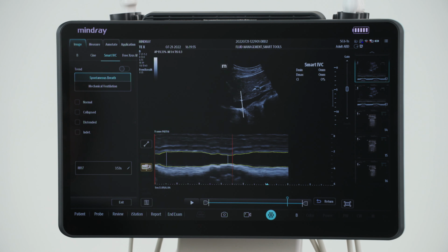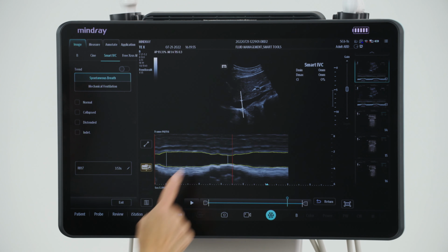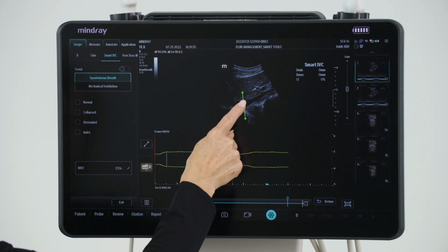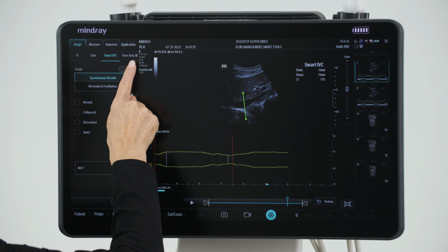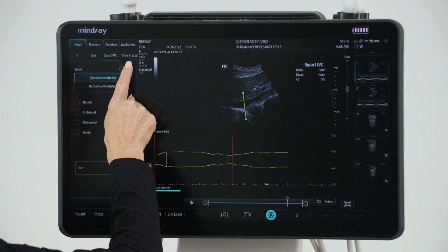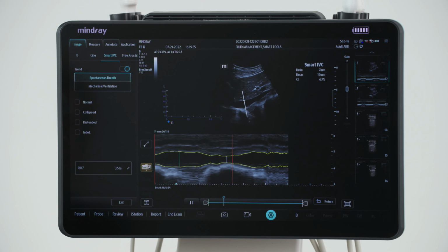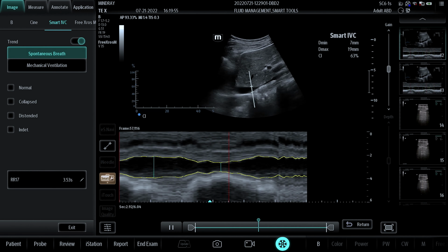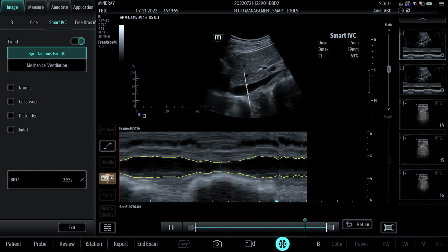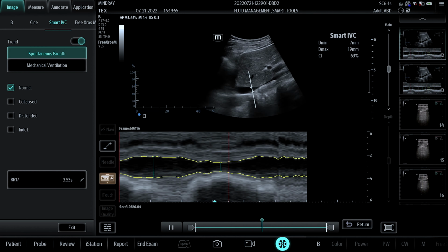If the sampling position is suboptimal, simply adjust the sample line in the reference image. Press the Trend tab to initiate a graph displaying the results over time, which will appear in the upper left corner of the imaging screen. Smart IVC will automatically calculate the respiratory cycle, but can be edited by pressing the RR tab located at the bottom of the tab. Smart B-lines.